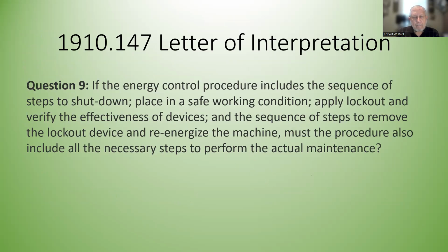Question 9. So that one, they kind of said, yeah, it might, maybe, if it has all the other things in it. If the energy control procedure includes the sequence of steps to shut down, place in a safe working condition, apply lockout, and verify the effectiveness of devices, and a sequence of steps to remove the lockout device and re-energize the machine, must the procedure also include all the necessary steps to perform the actual maintenance?